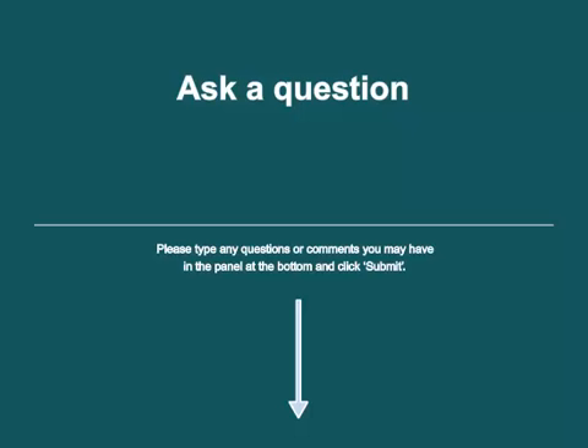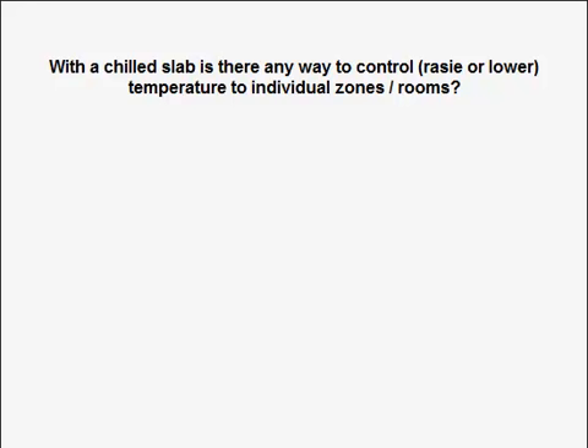A few more technical questions before we close. From Adrian Moore: with a chilled slab, is there any way to control, raise or lower temperature to individual zones and rooms? Yes, absolutely, you can zone it any way you like. The beauty of it is that if you vary the temperature of the water in your pipe work, you'll get a change in soffit temperature within about 20 minutes to half an hour. So compared to a system with natural or mixed flow ventilation, you've got much more rapid control. So yes, you can do it.